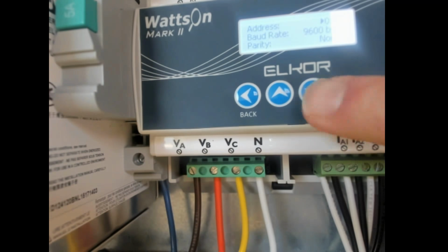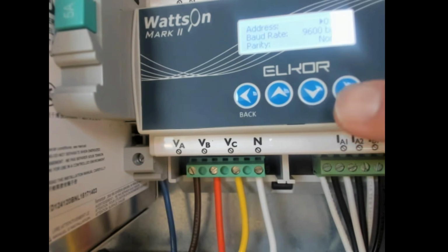You just select it, and then you'll go down in the option. Baud rate should be 9600 BPS, and then parity should be none. So let me just make sure I scroll through. Those are all good. Stop bits is going to be 1, and everything else could be on its default. Delay is 0.